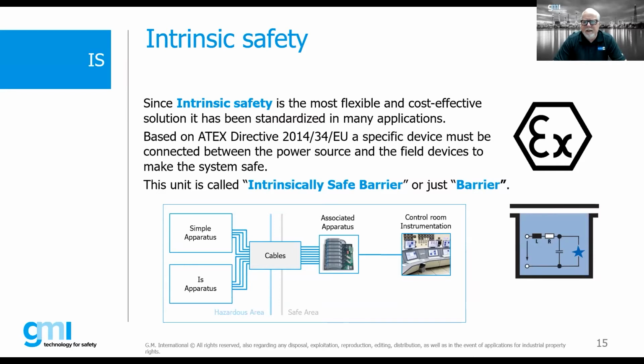Intrinsic safety is a system concept where we have to take into account what we call the associated apparatus. You'll hear this term, associated apparatus. That's basically what we call an intrinsically safe barrier. But that's only one portion of our loop, because we also have the outgoing power or control coming from our control room, with signals going through the associated apparatus via the cables out to the field devices. So it's a loop that we're talking about.